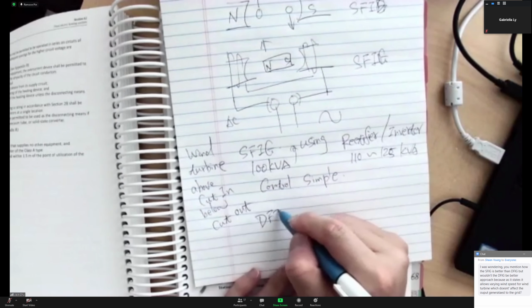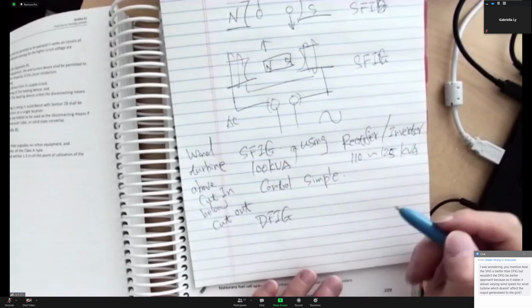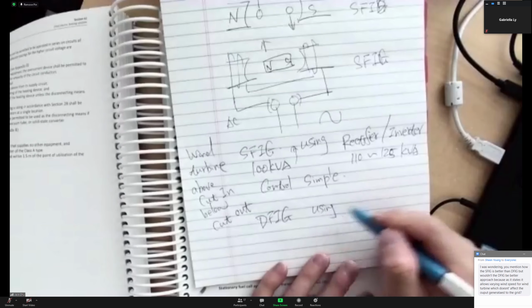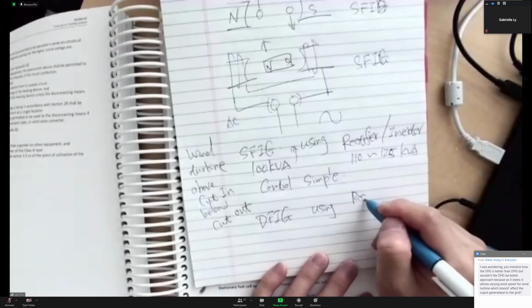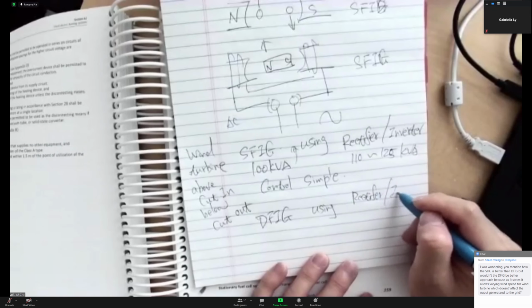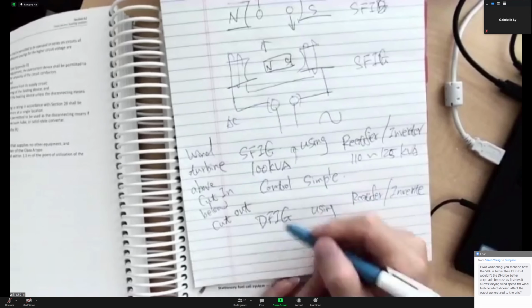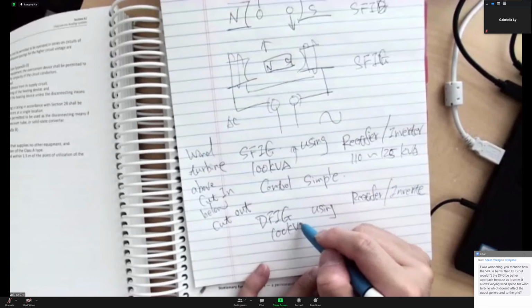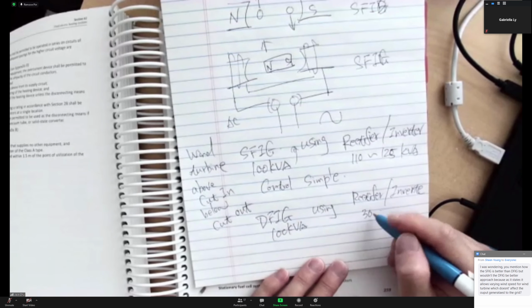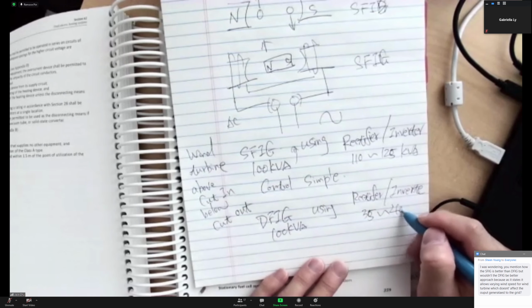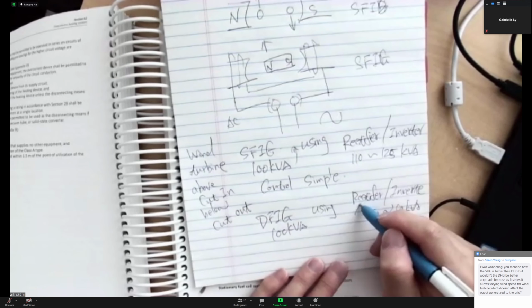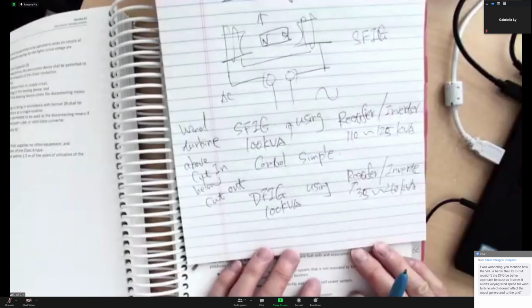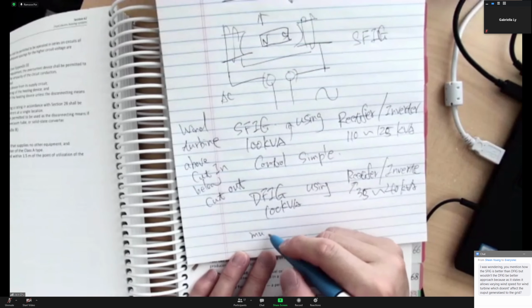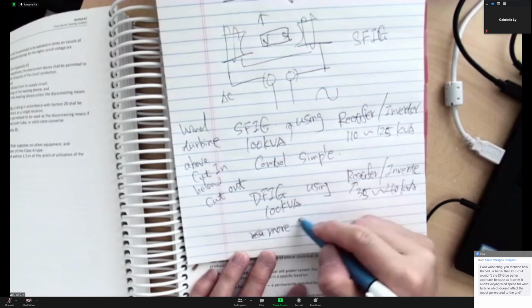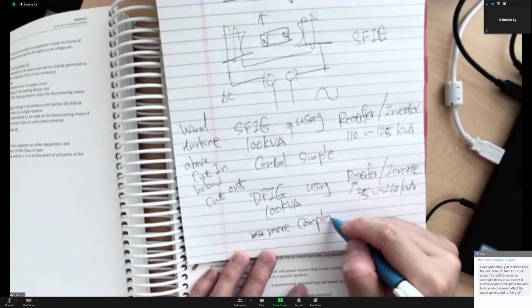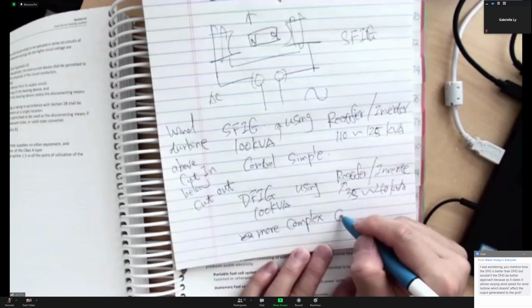And for the double feed induction generator, you also need to use this rectifier and inverter combination. But for this 100 kVA, you might just use 35 to 40 kVA, a smaller size, right? So it saves you money, but it will be a much more complex control required.